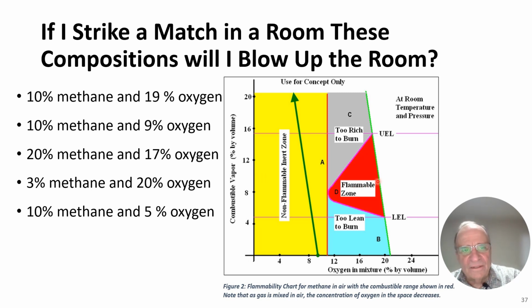19% oxygen is here. Will this blow up? Yes, it will. We're right smack in the almost stoichiometric position of the flammable zone. And stoichiometric means that you have exactly the right amount of oxygen to fully consume the fuel that you have available. Let's say I had 10% methane and 9% oxygen. Well, now I'm over here. So will that explode? No, it will not, because I'm in the non-flammable range.